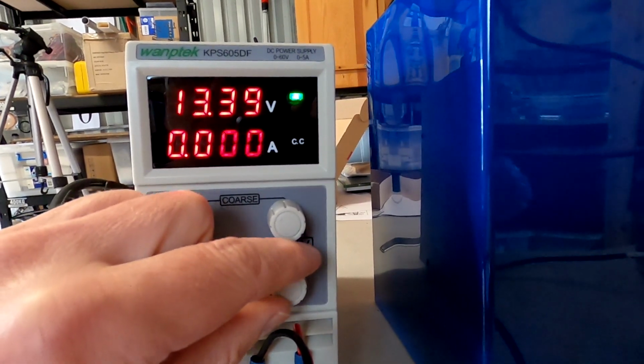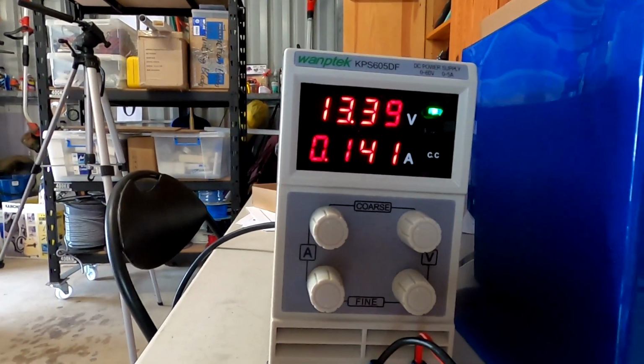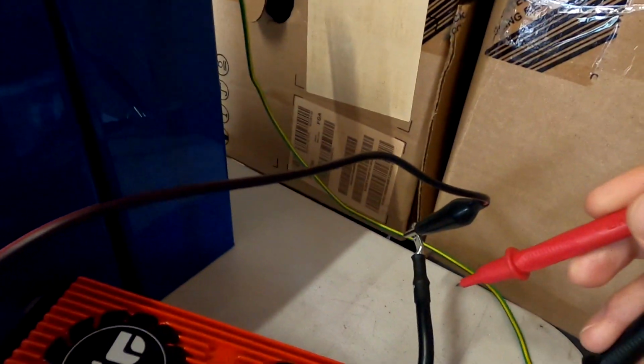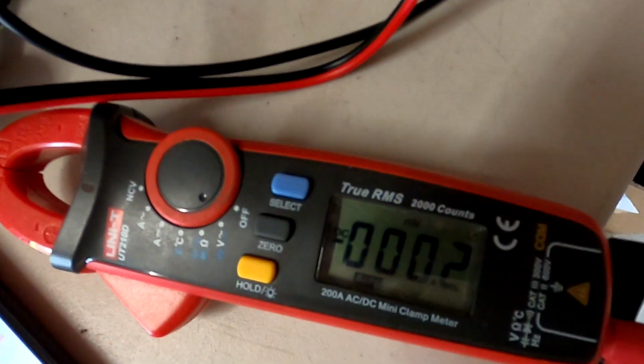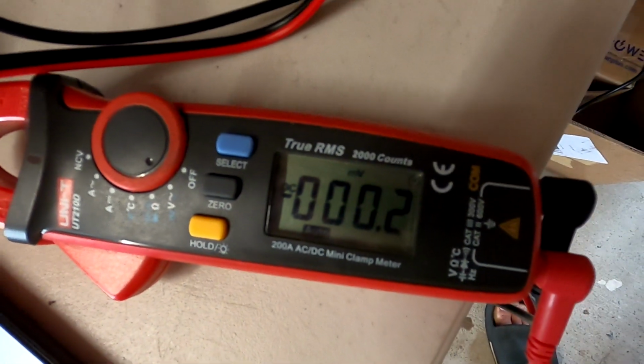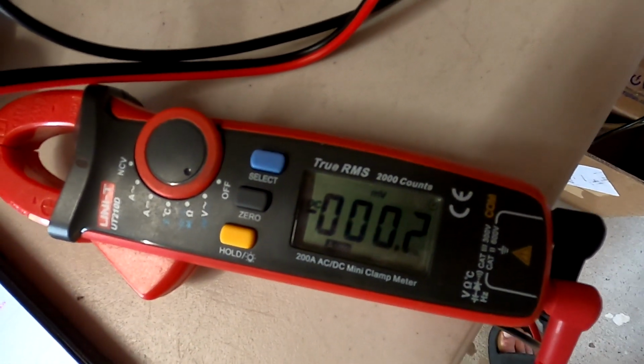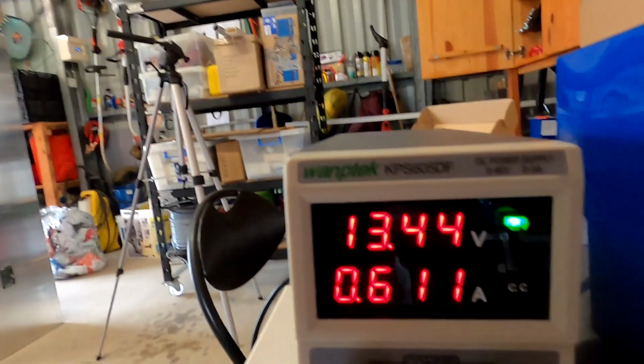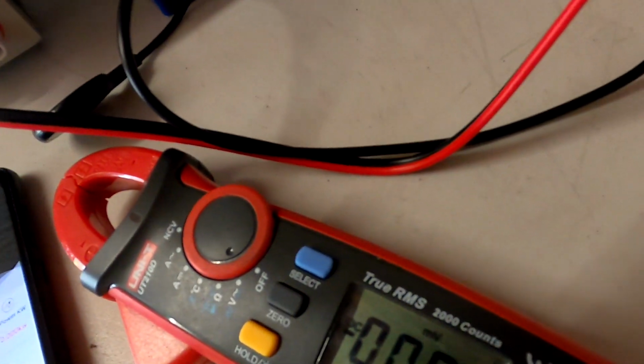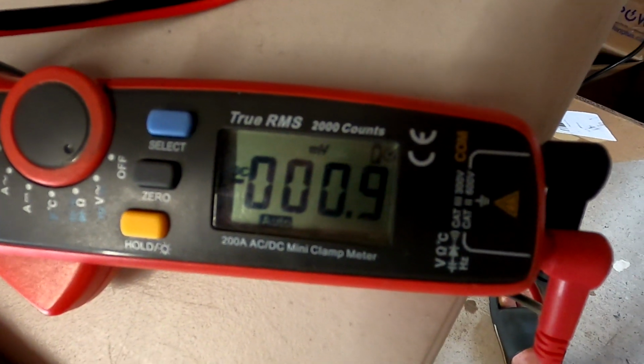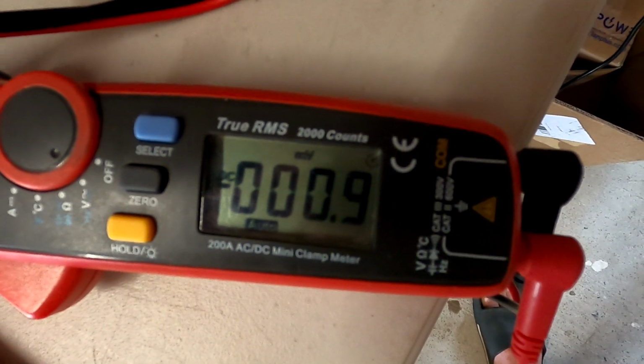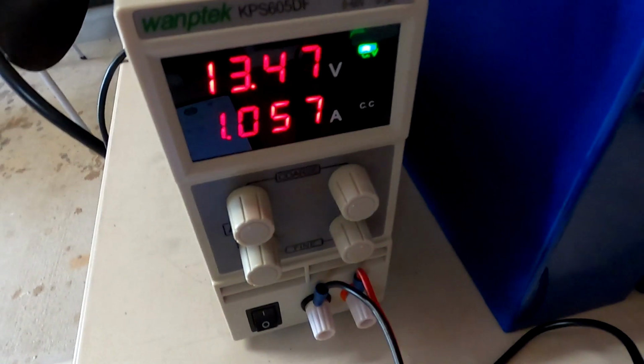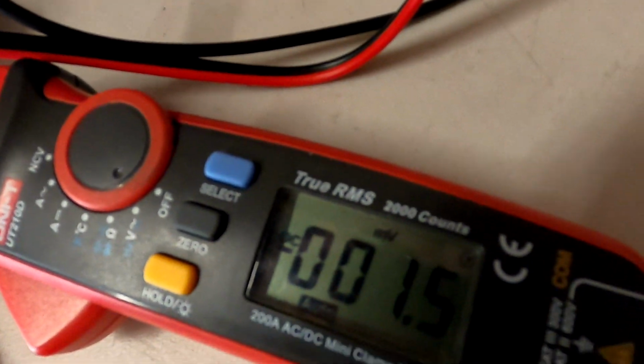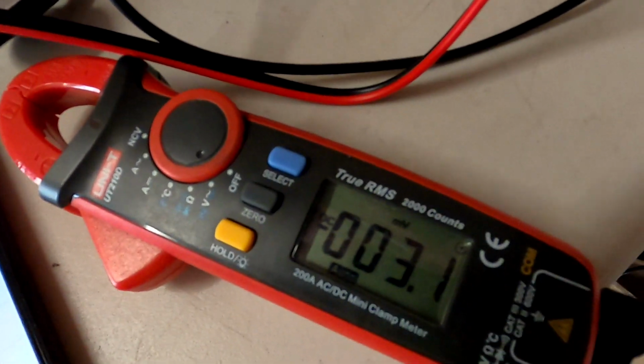Increase the voltage just a tiny bit, 140 milliamps flowing. The voltage drop here from the BMS is 0.2 millivolts, basically nothing. Okay, increasing the current: going to 0.6 amps, we've got 0.9 millivolts. Okay, going to 1 amp, 1.5 millivolts. 2 amps flowing, 3 millivolts.